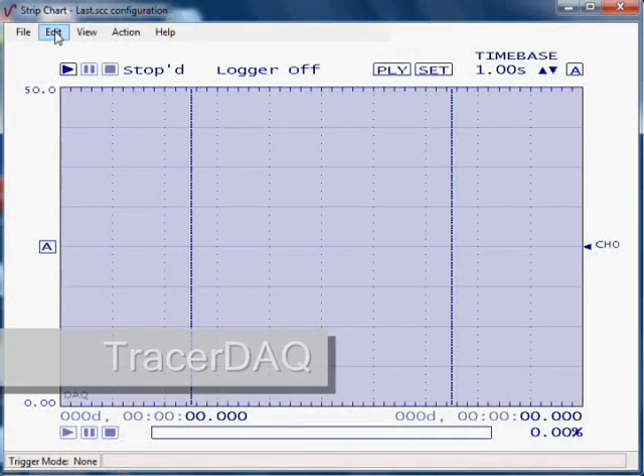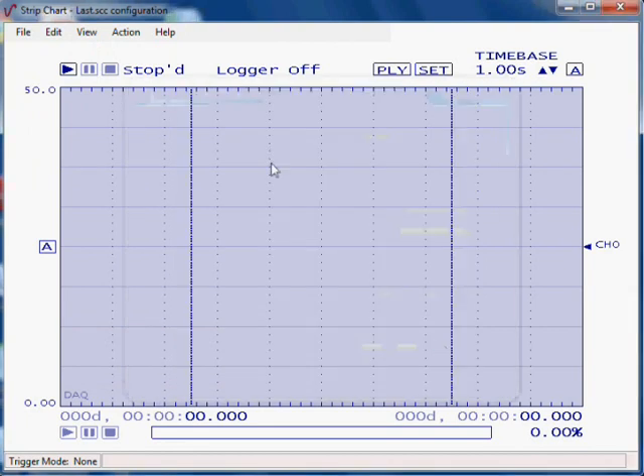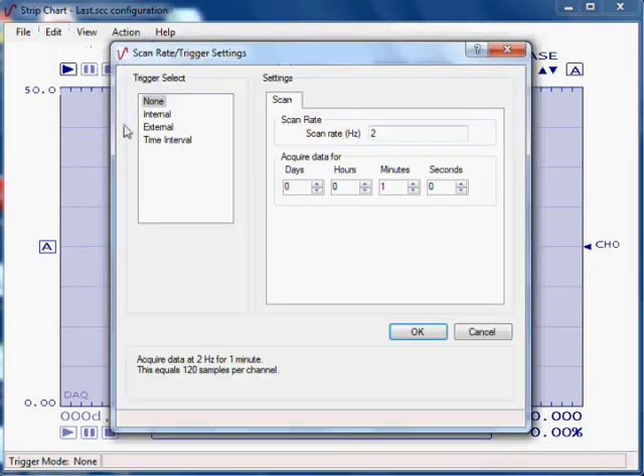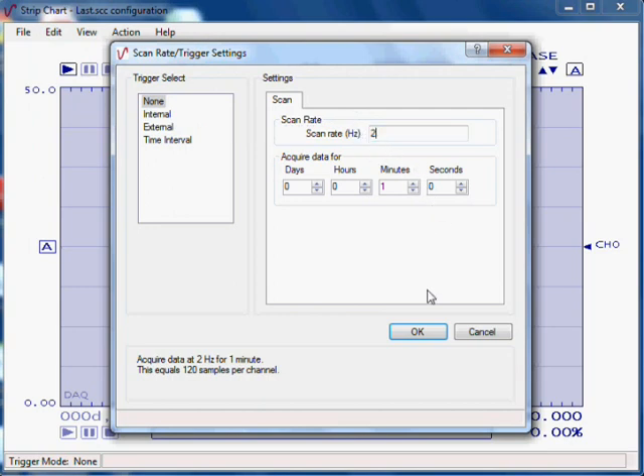Then, with the included TracerDAQ software, we select our channels and sample rate. The USB temp can sample data at up to two samples per second. It also provides 24-bit resolution for superior measurement accuracy.